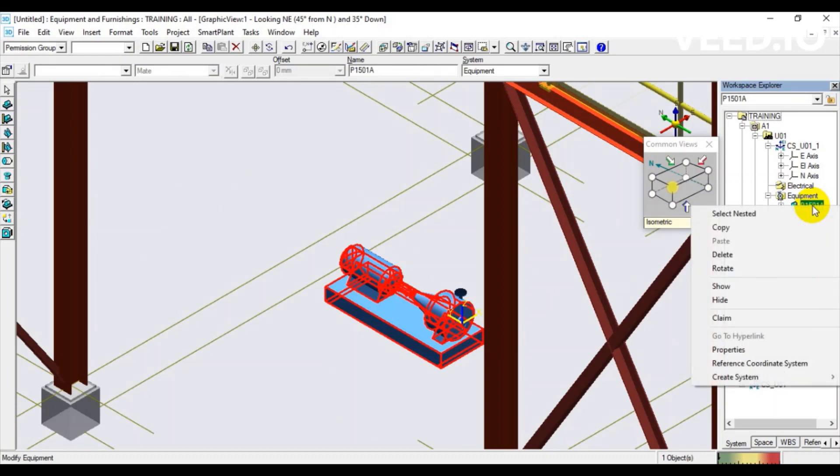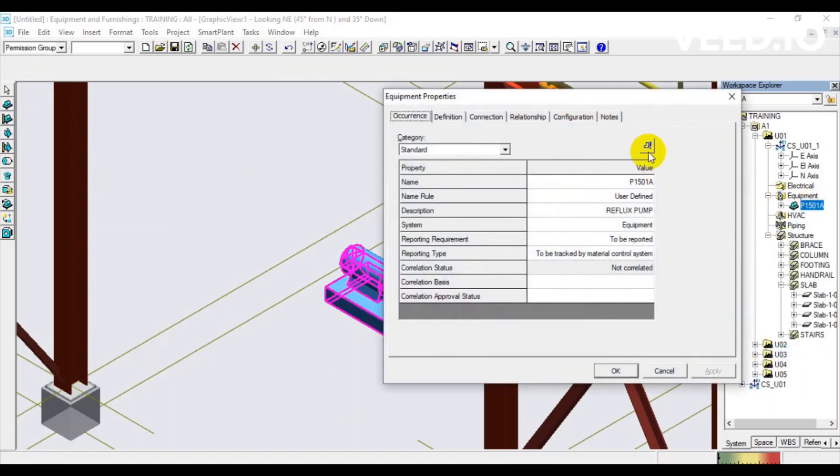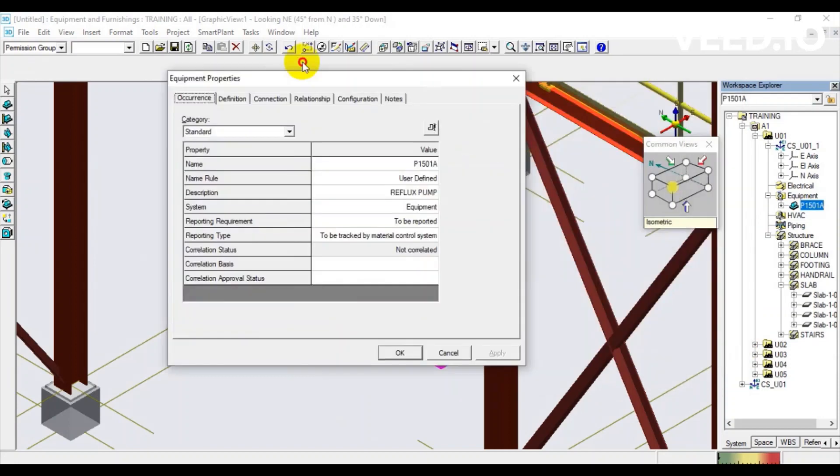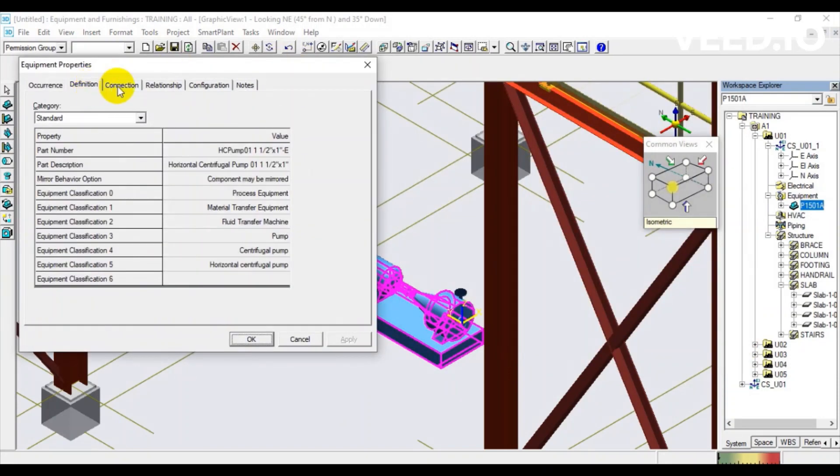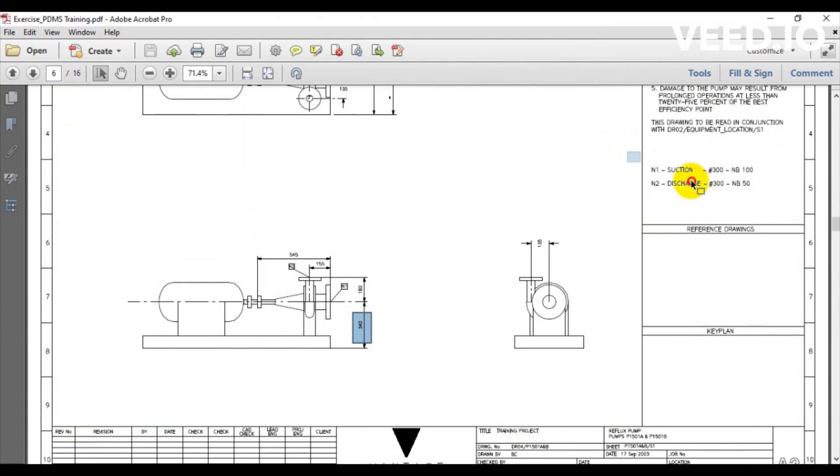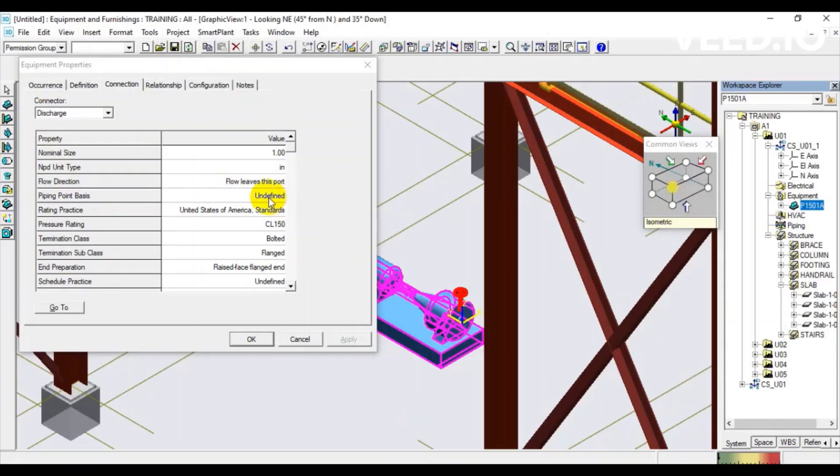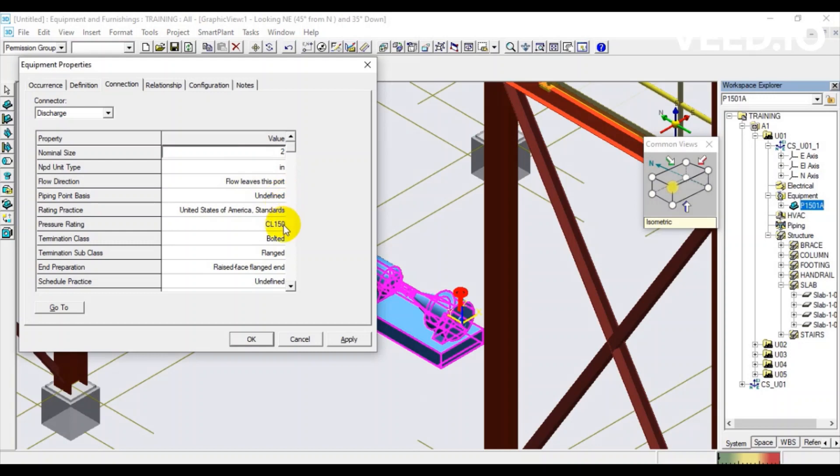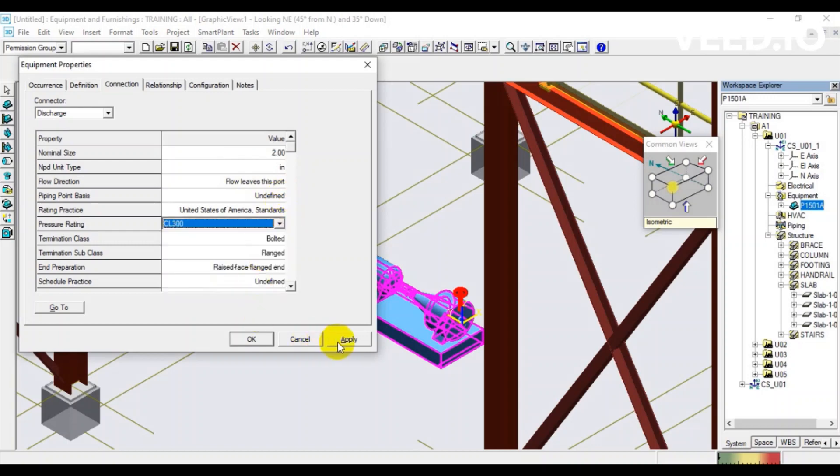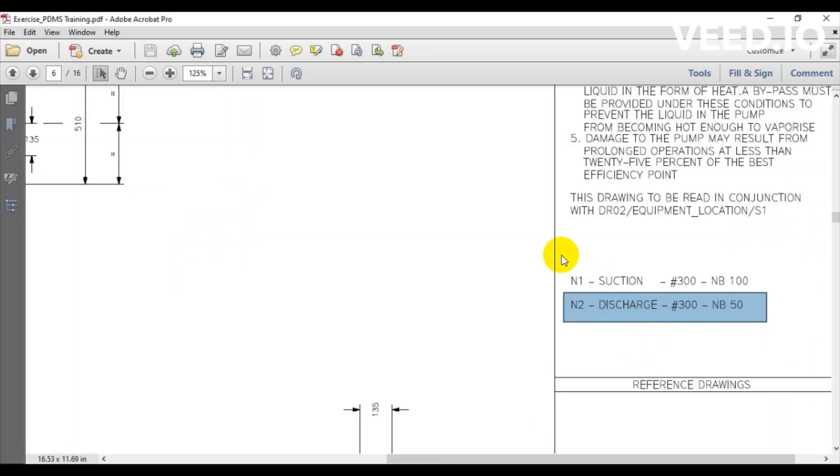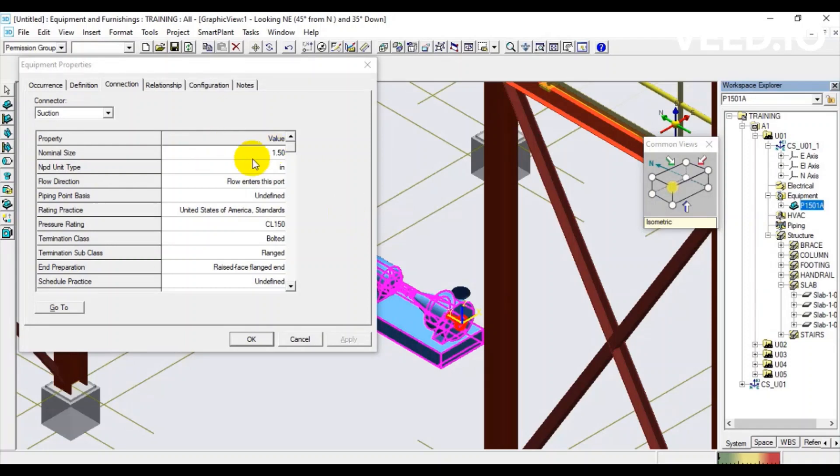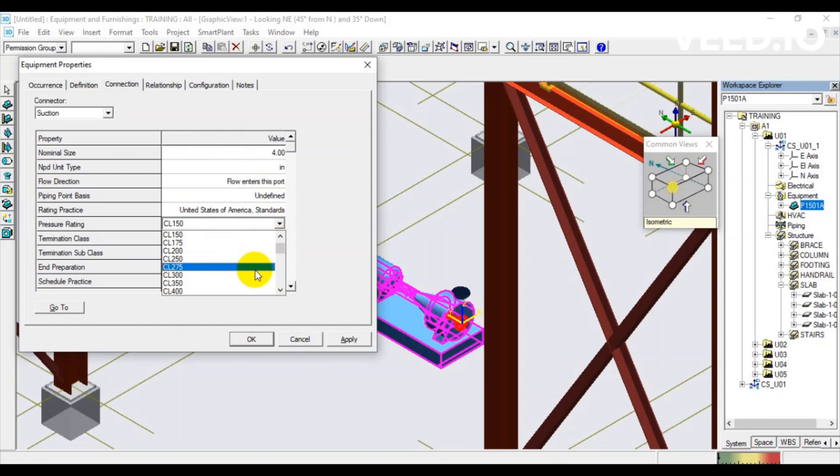Next task, we have to define the nozzle specification. Navigate to the connection tab. Choose discharge items then put nominal size 2 inch and pressure rating Class 300. Choose suction items then put nominal size 4 inch and pressure rating Class 300.